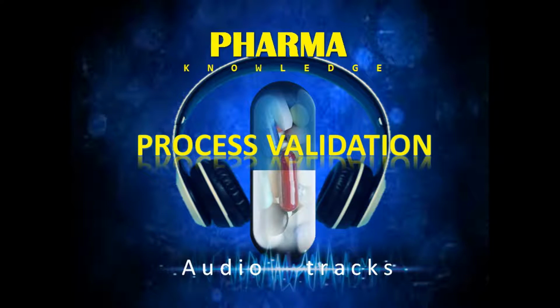D. Revalidation. Revalidation means repeating the original validation effort or any part of it, and includes investigative review of existing performance data. This approach is essential to maintain the validated status of the plant, equipment, manufacturing processes and computer systems.